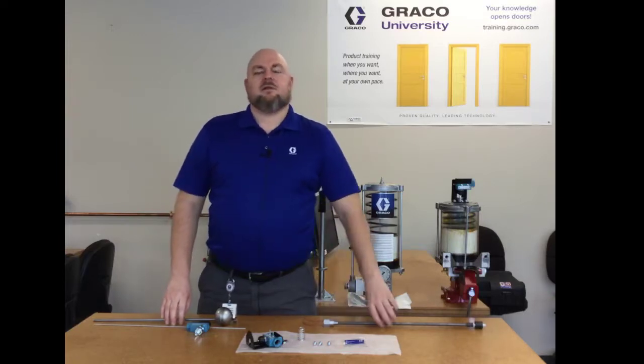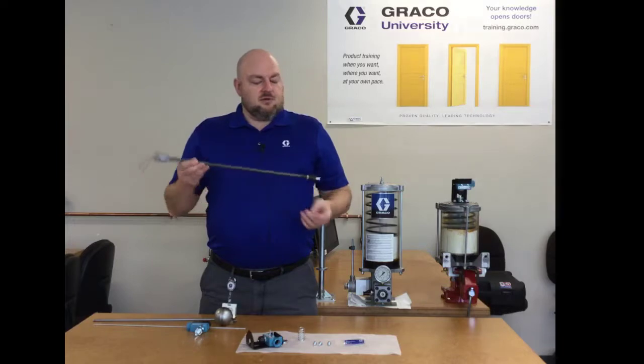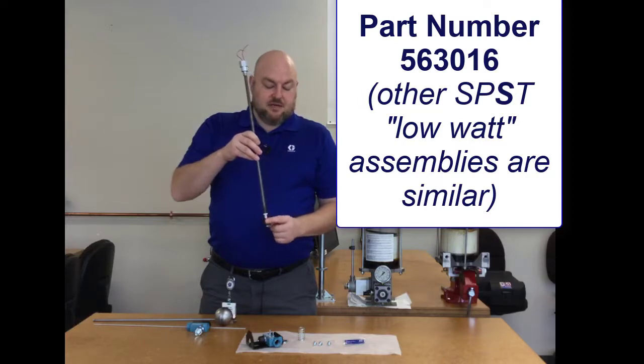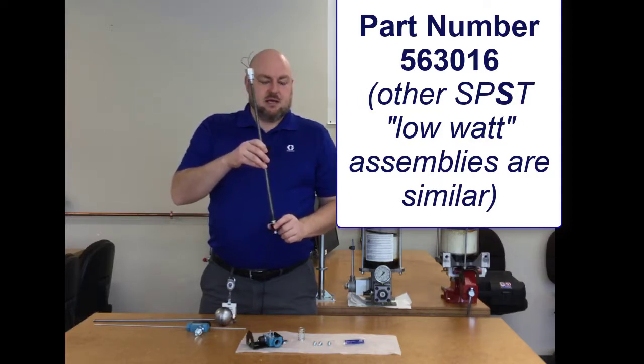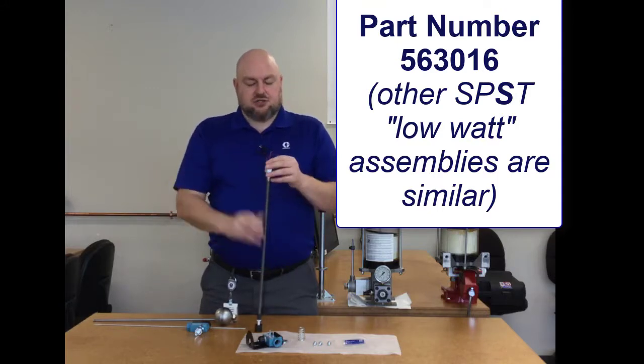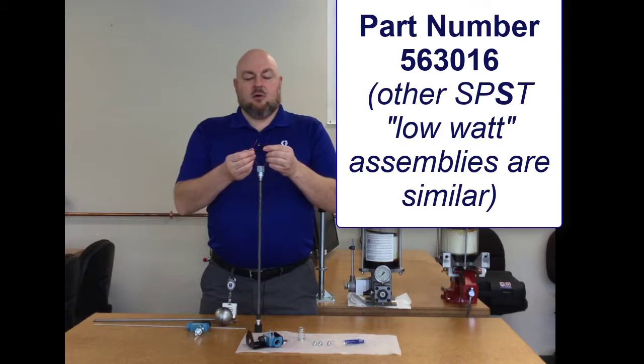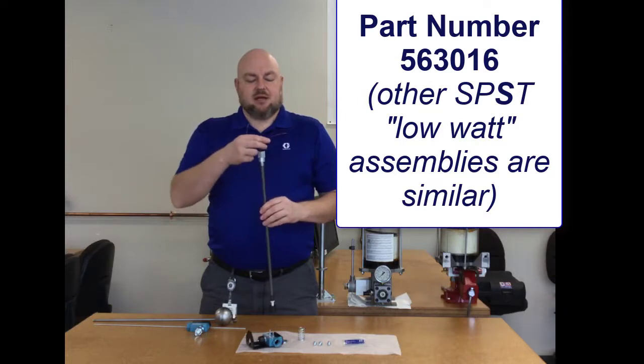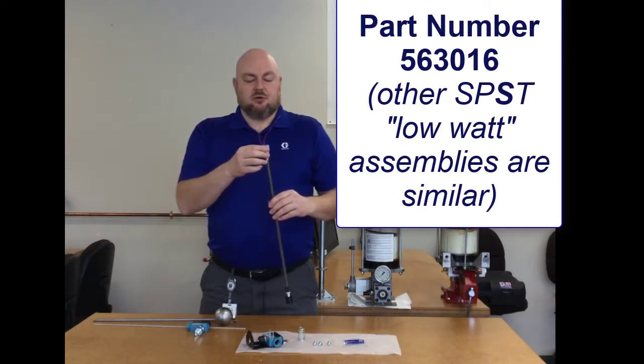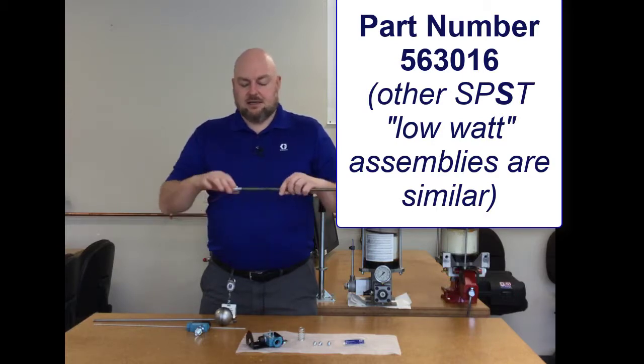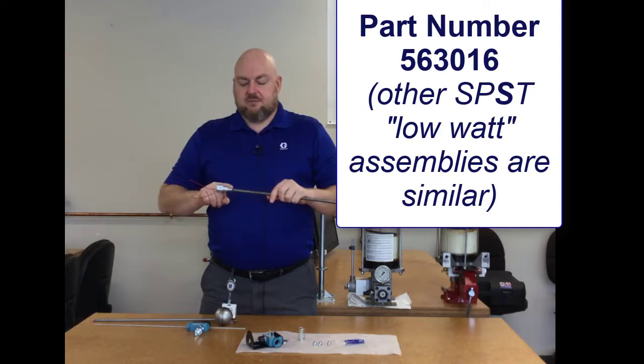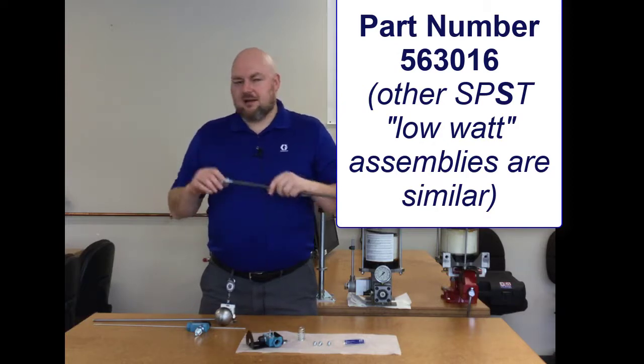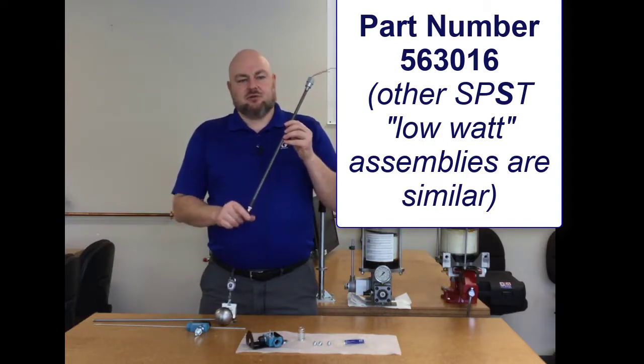For oil there are a couple of different options. The most economical option is this simple float where there's just a little float on the bottom. The float itself can be removed and flipped over if you want to change the normal state, so you can set this up to be normally open or normally closed. There are just two wires coming out the top and they're both the same color because it doesn't matter which way you wire it. It's just a dry contact switch making and breaking a circuit, so all you got to do is hook up your two wires to your controller or your PLC and send some power through that. These things mount on a 1¼ inch NPT thread and there's a pipe plug in the top of each reservoir on the oil reservoirs. This is your more economical option, just a real basic float switch.